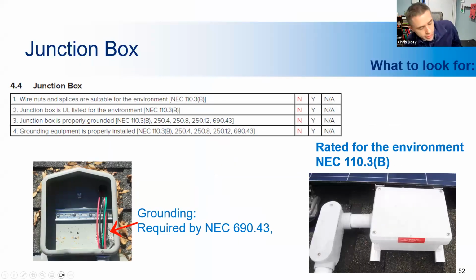All right, so the next part of the system that we're going to look at is junction boxes. This is basically any enclosure that has electrical connections running through it. So if an enclosure is mounted on the roof deck, it has to be properly flashed and sealed. As you can see on the left, this is properly flashed and sealed. A conductive enclosure, which is essentially a metal enclosure, is considered likely to become energized, and it also has to be properly bonded per NEC requirements. This junction box actually wasn't.